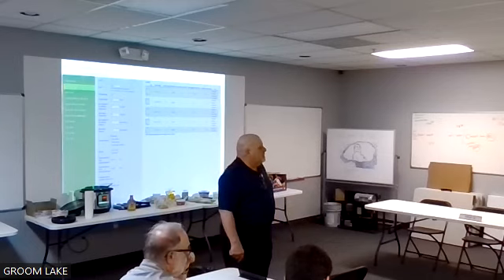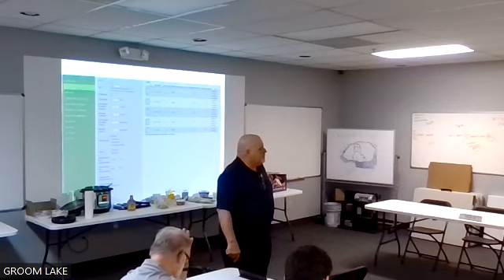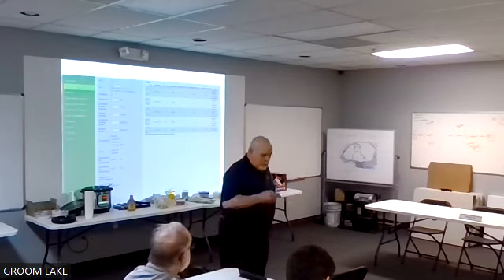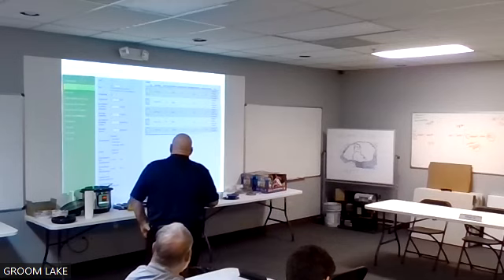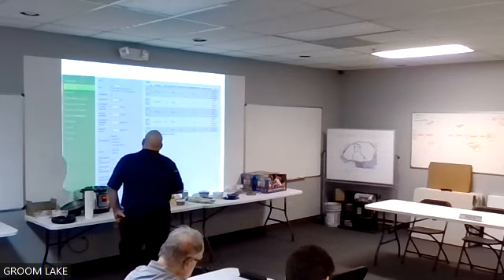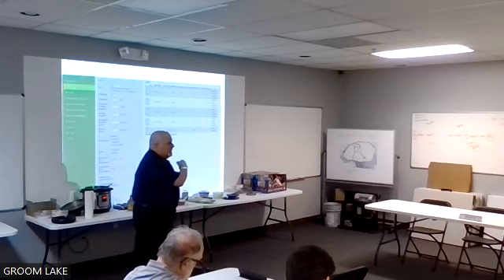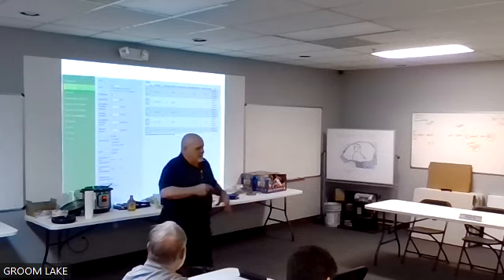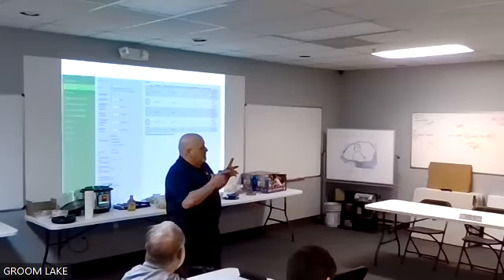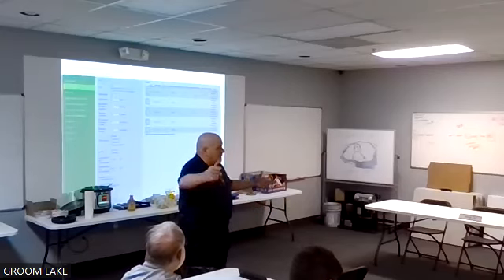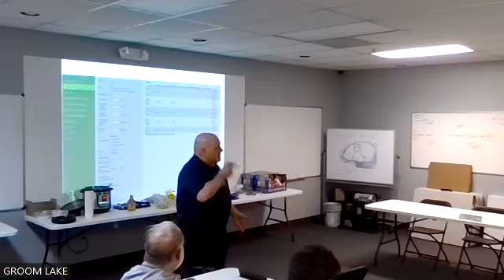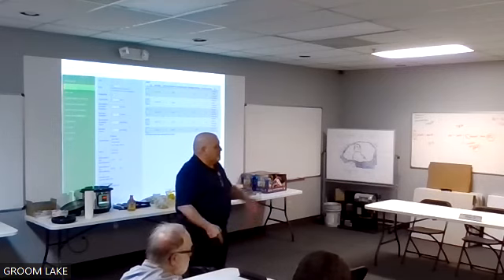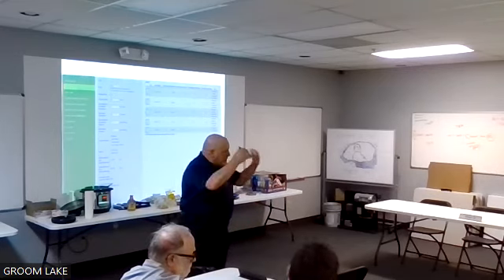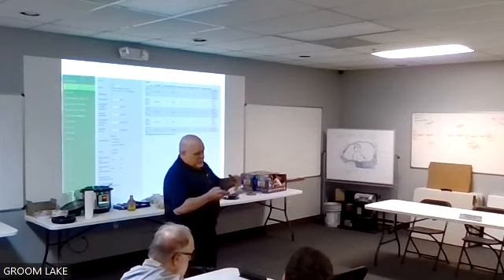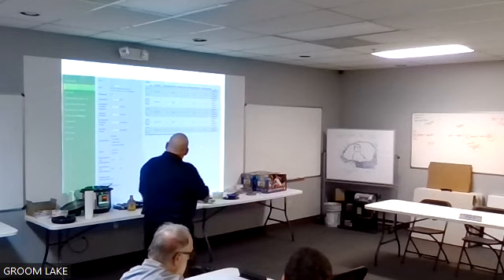So, have you ever had to get the length of all the pipe and the size of the pipe? That's ideally what you want to do with this program. See right here, they ask you for your system volume. That's where you would enter that number. You take the diameter of the pipe, the radius squared times pi times the length of the pipe gives me a volume, times 7.45 gallons per cubic foot. And you do that for every pipe size. I come up with 800 gallons. I stick that 800 here.